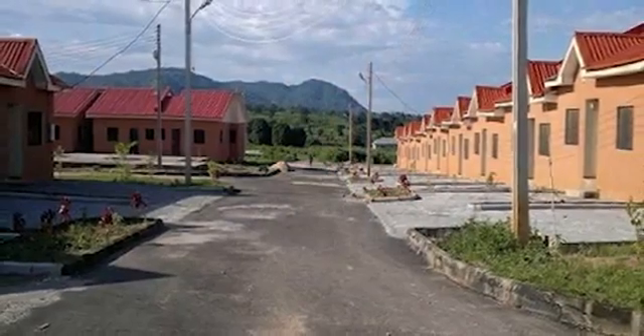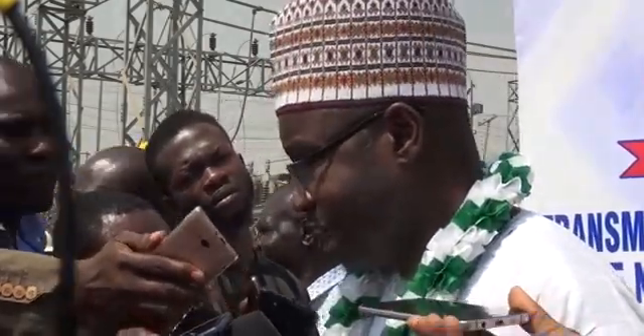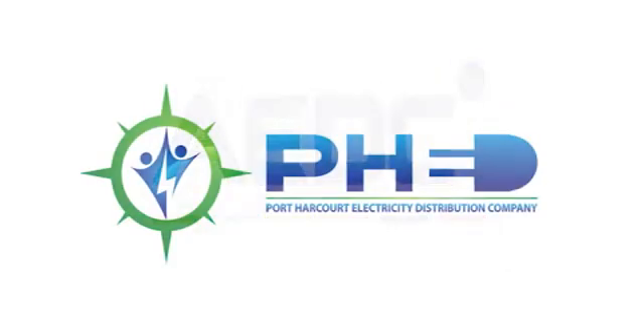But generally, distribution has to get investment. We, TCN, it is in our interest, and in the interest of even the expansion we are doing, that there is some investment coming into distribution. Because if you look at out of the 738 interfaces that we have with the discos, only 421 are completely covered by protection, meaning the remaining 300 and something are not covered by protection, which means any fault on people's houses can hit our transformer. And that has led to several of our transformers getting bad.